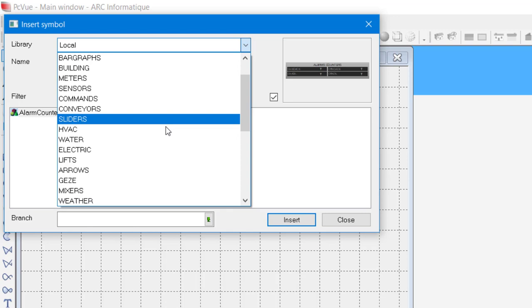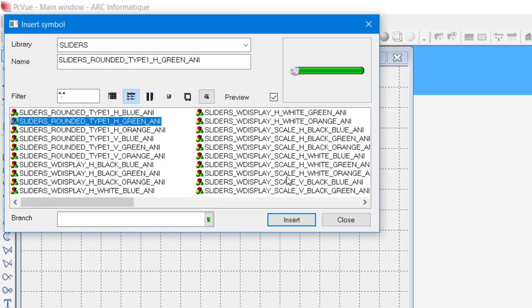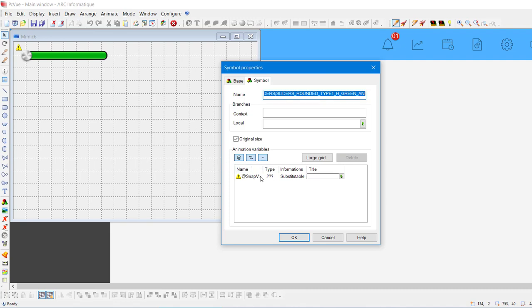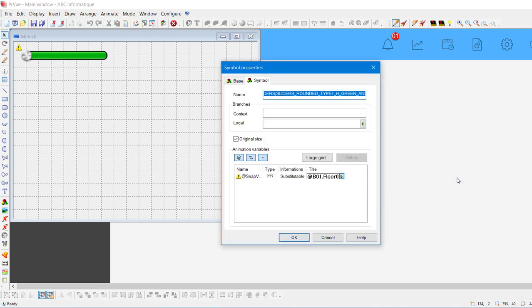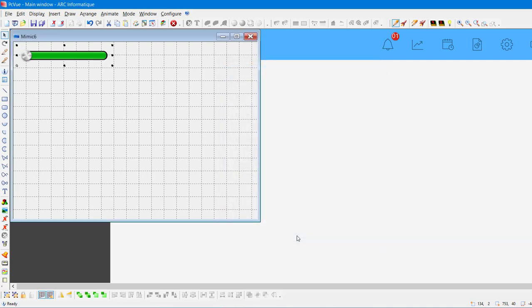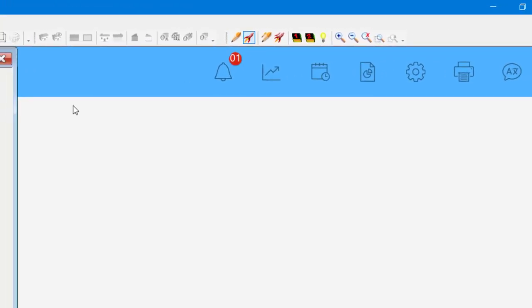Symbols are organized in categories. For our project, we need a slider. The second one will do well. Let's insert it. Here, you can see the parameters of the new symbol that we created. We need to connect the animations of the symbol to a variable. To do so, we can select a variable from our database here. Just click on this button and choose the variable TempSet. The symbol is now inserted. Let's switch to Run Mode and check if it works. Perfect.